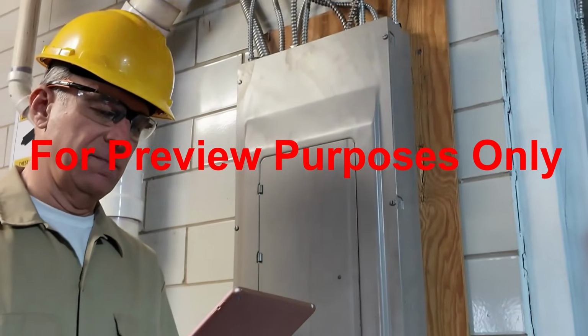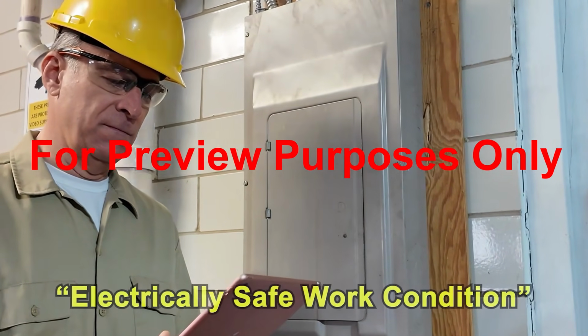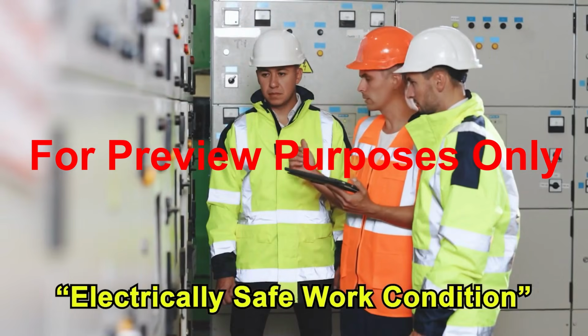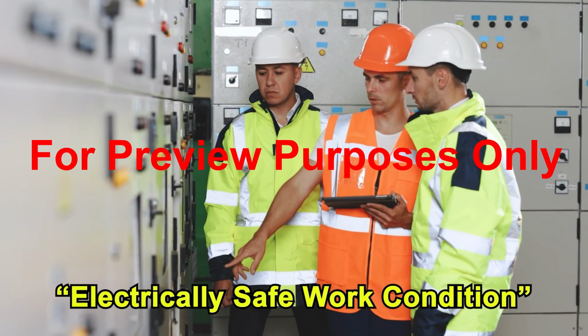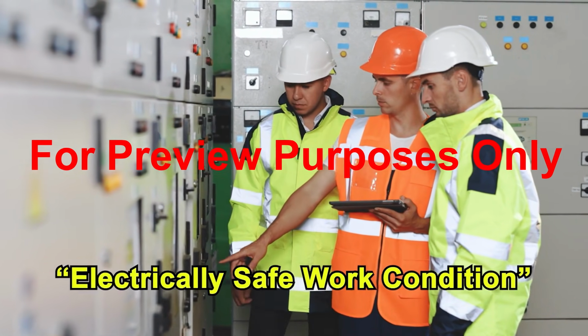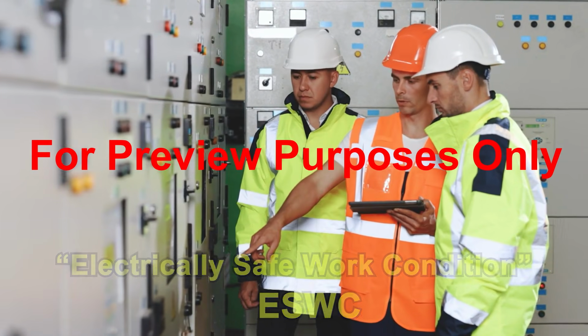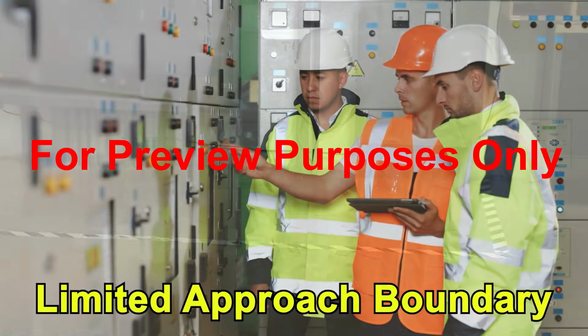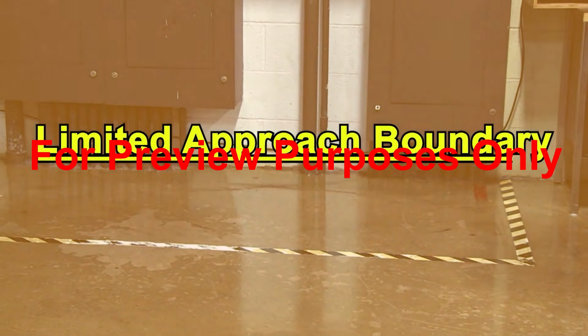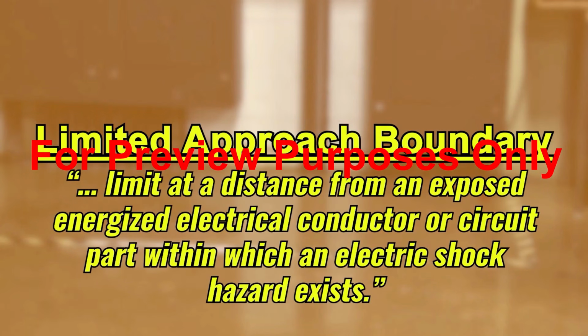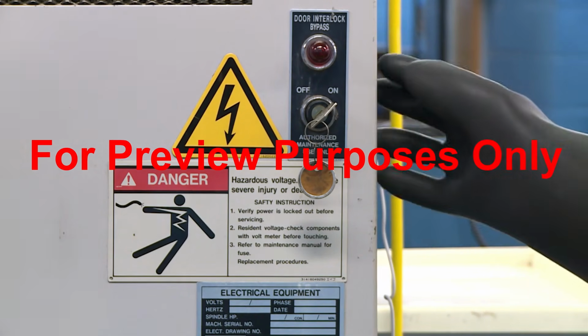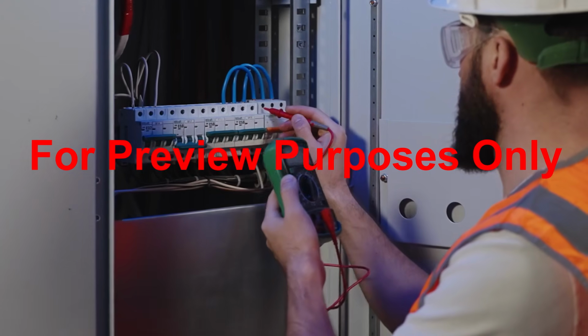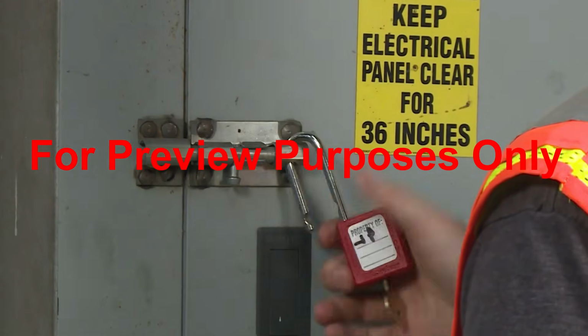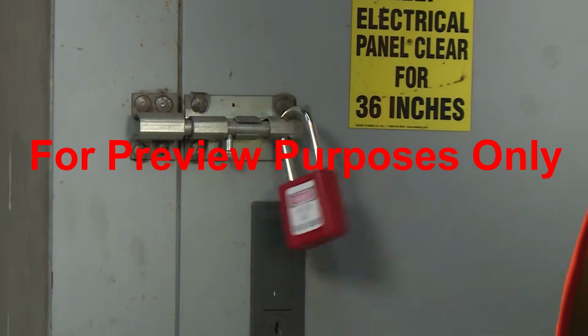One of the most integral parts of an electrical safety program is its electrically safe work condition policy. The NFPA 70E standard requires you to establish an electrically safe work condition, ESWC, when working within a piece of equipment's limited approach boundary. The limited approach boundary is defined as the limit at a distance from an exposed energized electrical conductor or circuit part within which an electric shock hazard exists. So establishing an electrically safe work condition involves turning off power, verifying there is no electricity present, and ensuring the equipment cannot be re-energized while you're working on it.